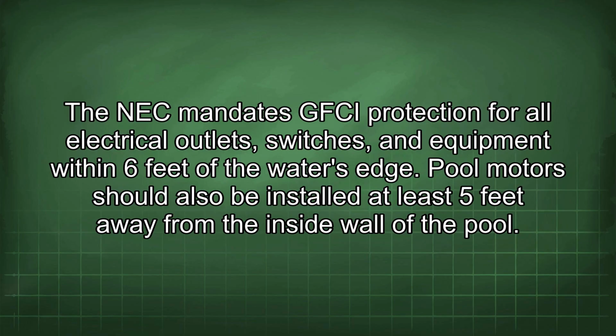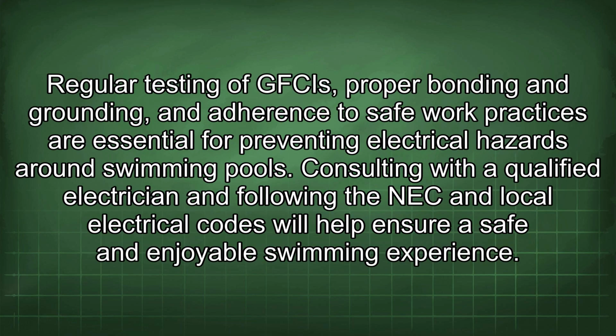In summary, GFCI protection is a critical safety requirement for pool motors and other electrical equipment around swimming pools. The NEC mandates GFCI protection for all electrical outlets, switches, and equipment within 6 feet of the water's edge. Pool motors should also be installed at least 5 feet away from the inside wall of the pool. Regular testing of GFCIs, proper bonding and grounding, and adherence to safe work practices are essential for preventing electrical hazards around swimming pools. Consulting with a qualified electrician and following the NEC and local electrical codes will help ensure a safe and enjoyable swimming experience.